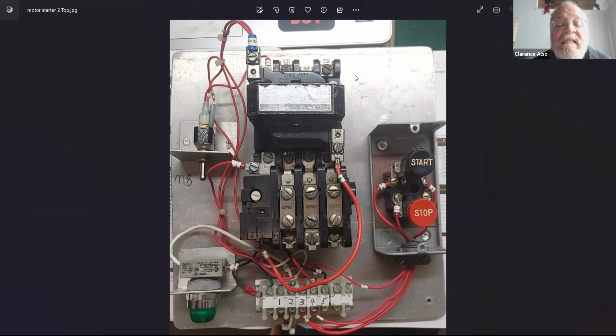Between 5 and 6, those terminals there, this is a spring-loaded stator or armature in your starter coil. That's going to slap down anytime you energize the thing. It's going to go clop, and you're going to know something happened. And then if you take your finger off the button, it should stay down if your holding circuit's working right.